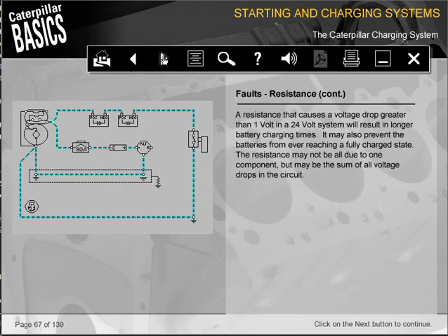A resistance that causes a voltage drop greater than 1 volt in a 24-volt system will result in longer battery charging times. It may also prevent the batteries from ever reaching a fully charged state. The resistance may not be all due to one component, but may be the sum of all voltage drops in the circuit.